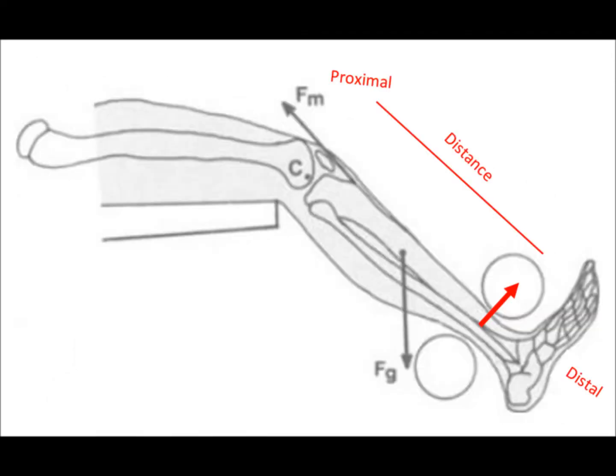As the user operates the machine, a strain gauge force transducer located at the distal side of the lever arm records the force being applied by the user's limb. Since the resistance force will be applied at the proximal end of the lever arm, this force is recorded as a torque according to the distal distance between proximal end and strain gauge. This recording is then converted to an electrical signal by the transducer.